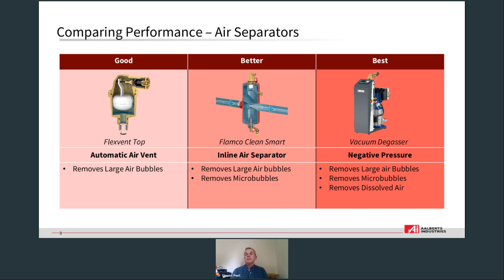The 90 degrees C comes from the fact we can drop the pressure to atmospheric pressure. Water boils at 100 degrees C, and that's why we have that limit. Also, at the other end of the scale, we can operate at around 10 degrees C and pull a vacuum all the way down to 0.2 bar, and that's really removing all the dissolved air which is in the water, which is the problem in the systems as it comes out. It degasses when required. There's a gas sensor at the top of the unit which samples the water and switches the unit off when no gas is detected, and that's why we refer to it as the Vacumat Eco. So that's air in systems.